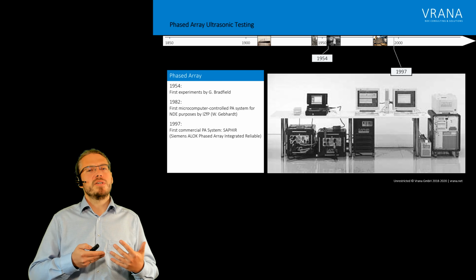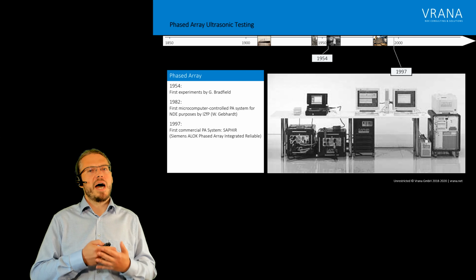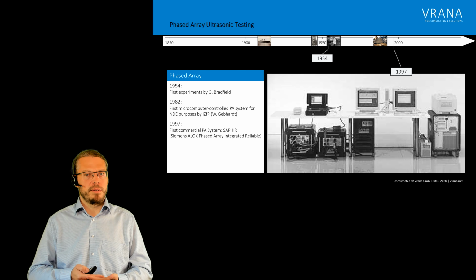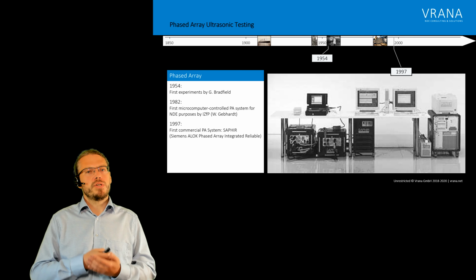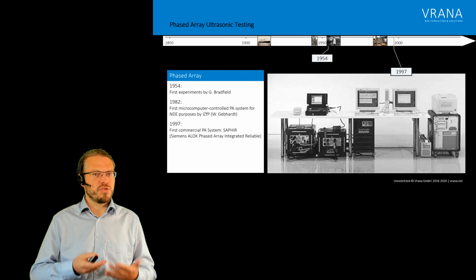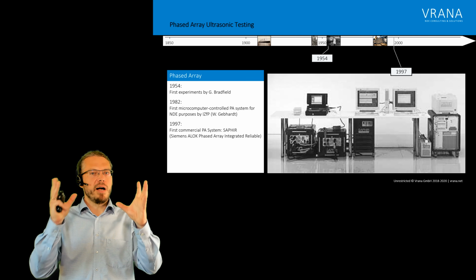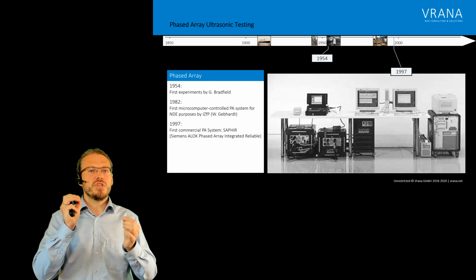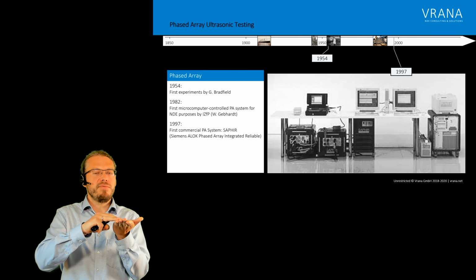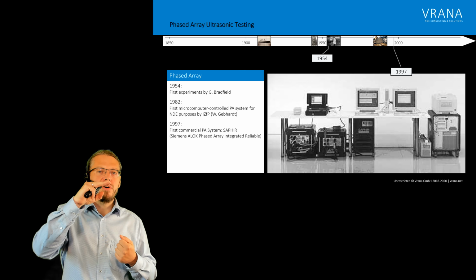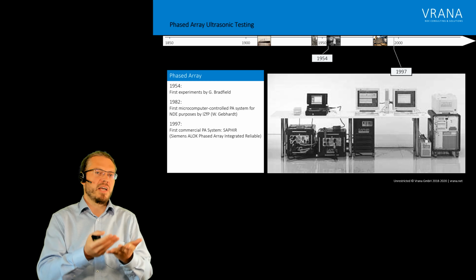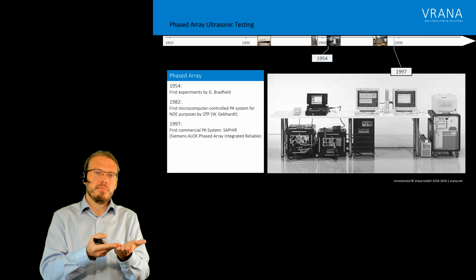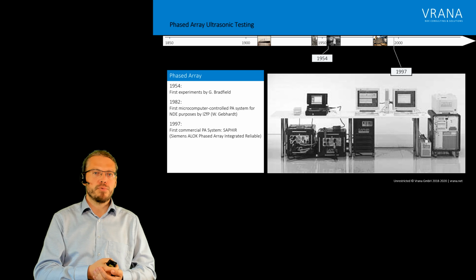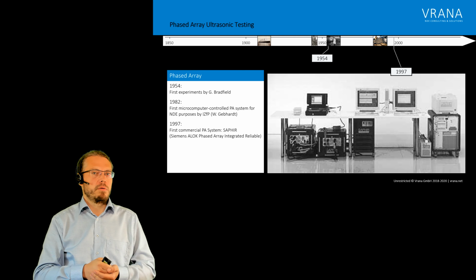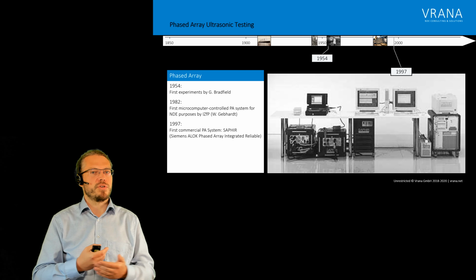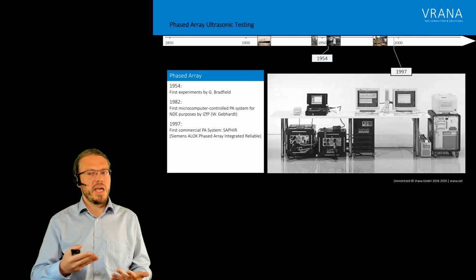But this video is not about the history of phased array. This video is about how phased array ultrasonic testing works. In the last video, we talked about how conventional ultrasonics works. We have an ultrasonic instrument that produces a strong pulse, which is connected to a probe, and its active element produces a short excitation, which travels through the component. If there is anything within that component, like a flaw or a back wall, the wave is reflected and travels back to the transducer, where it is received by the same probe. Depending on the time the signal needs to reach that indication and come back to the surface, we can calculate the depth of our indication.